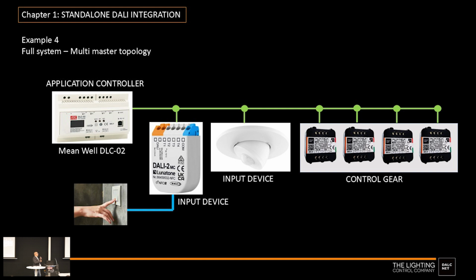This is another quite simple application, but the idea is that especially with DALI 2, new input devices are not masters anymore—they're not sending commands directly to the luminaires. The input device, like a push button interface or a presence sensor, sends what is called an instance: a message that doesn't control the luminaire directly, but just tells another device that the button is pressed or presence is detected.